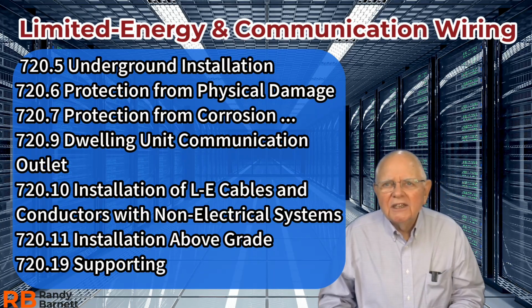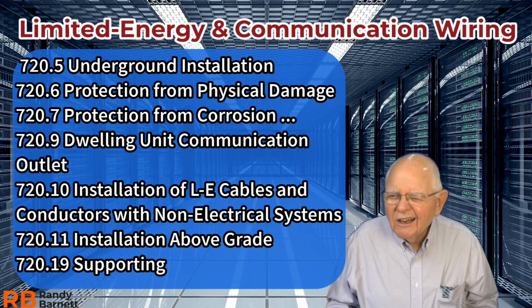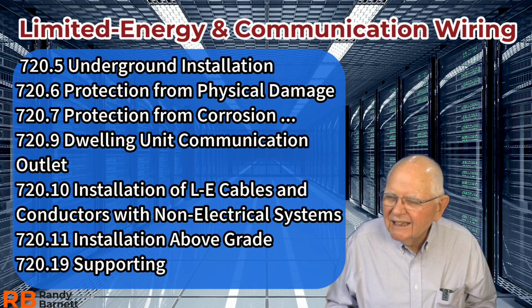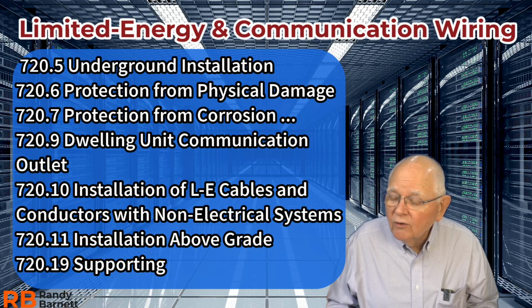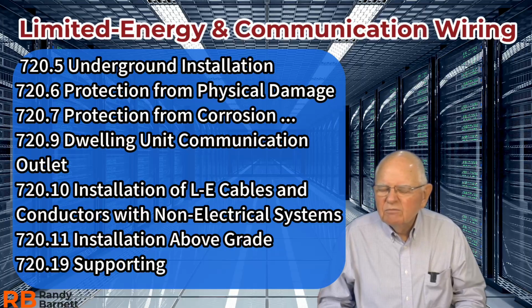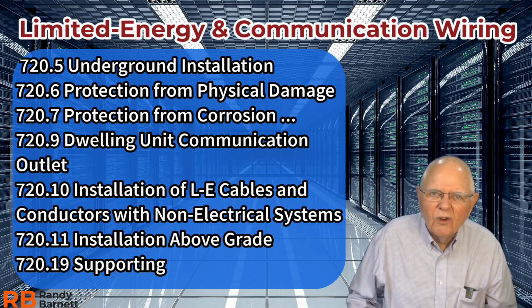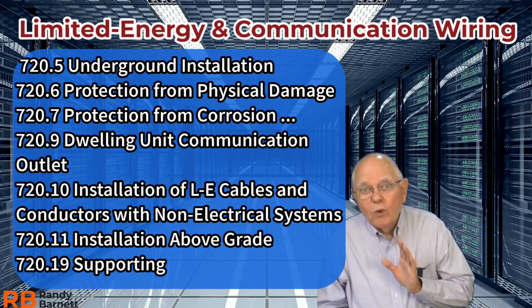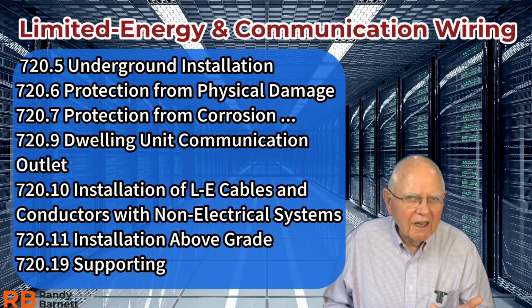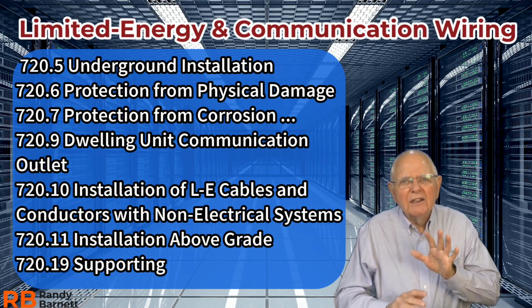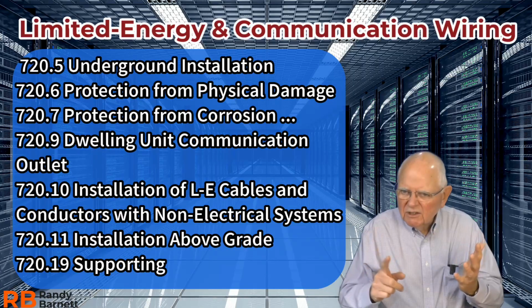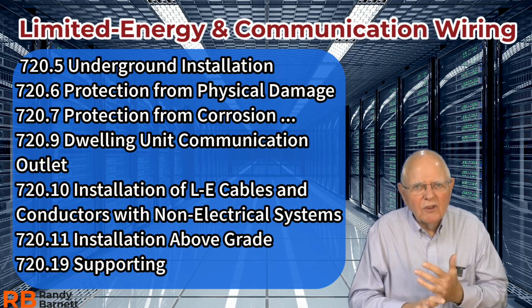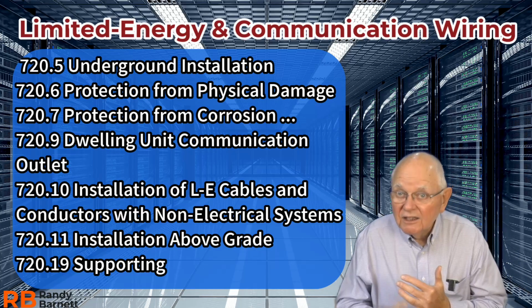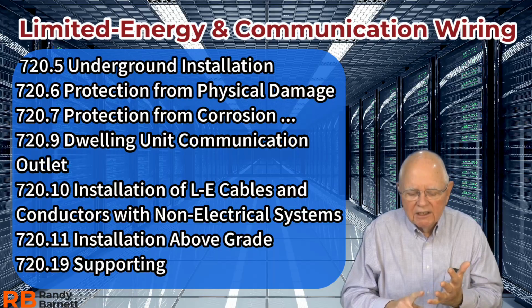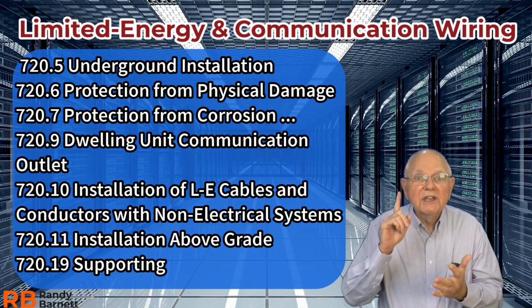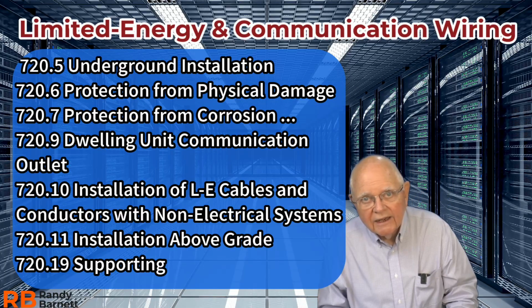720.10 talks about installation of limited energy cables and conductors with non-electrical systems. Doesn't sound like a good idea, huh? It says don't intermix them is what it's telling us. Don't intermix your limited energy systems with mechanical type systems, piping, plumbing, and so on and so forth. Limited energy systems in wet locations above grade, I mentioned 720.11 before, but nonetheless, it talks about above grade being considered a wet location. Then I would have to use conductors that are marked and listed for a wet location. However, exceptions again, as I mentioned, for fiber, communications cable, coax, and network-powered broadband low-power cable.